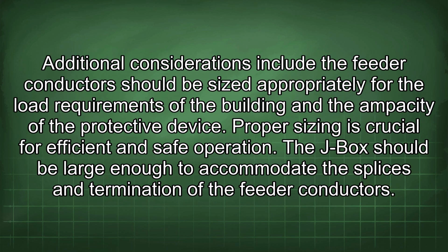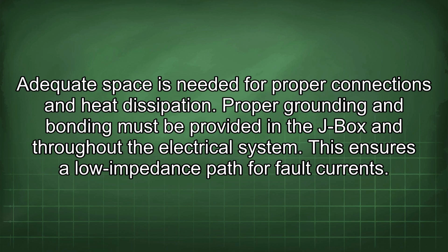Additional considerations include the following. The feeder conductors should be sized appropriately for the load requirements of the building and the ampacity of the protective device. Proper sizing is crucial for efficient and safe operation. The J-box should be large enough to accommodate the splices and terminations of the feeder conductors. Adequate space is needed for proper connections and heat dissipation. Proper grounding and bonding must be provided in the J-box and throughout the electrical system. This ensures a low impedance path for fault currents.